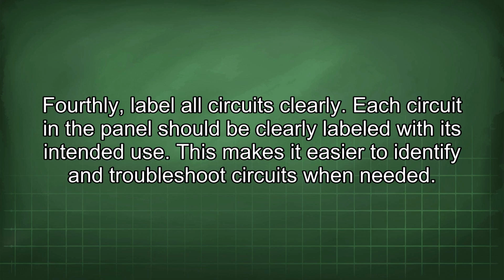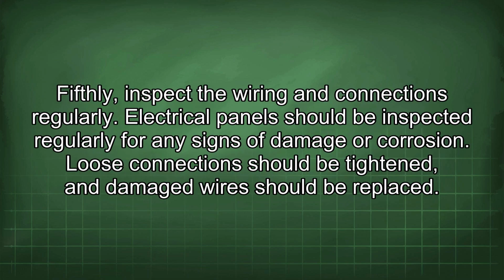Fourthly, label all circuits clearly. Each circuit in the panel should be clearly labeled with its intended use. This makes it easier to identify and troubleshoot circuits when needed. Fifthly, inspect the wiring and connections regularly. Electrical panels should be inspected regularly for any signs of damage or corrosion. Loose connections should be tightened, and damaged wires should be replaced.